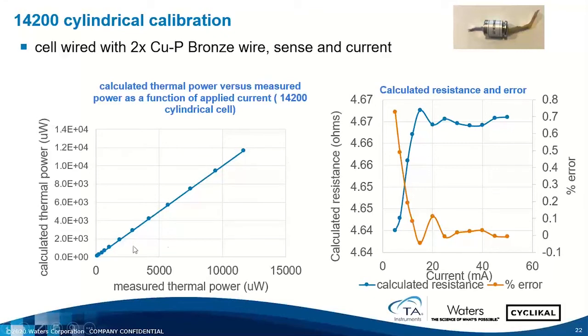Typically, we're working more down in this range. On the right here is a plot of the calculated resistance, and on the right-hand axis here is the percent error. Typically, for a lot of our experiments lately, we're working in the 20 milliamp range. That's the area that we tend to calibrate in. And you can see we get pretty decent accuracy of the thermal power going through that calibration.